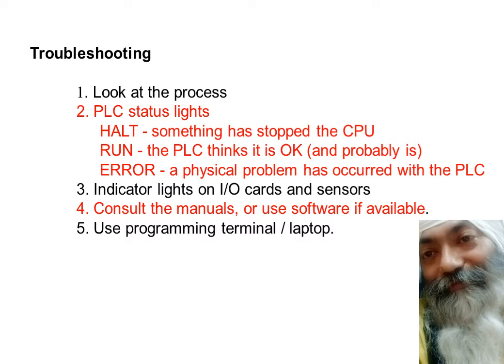So that's the way we need to use a programming terminal or laptop to know the status of each and everything. Once you see the error or any LED, the moment you connect a programming terminal or laptop to it, of course if it's a laptop, it has to have a dedicated program which converts your laptop into a programming terminal, you will get a number of error messages written in text, and the possible way to troubleshoot can also pop up in a window. That kind of thing is also possible, again depending upon the model and the software which you are using.